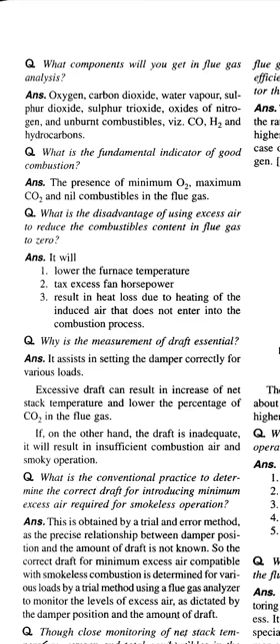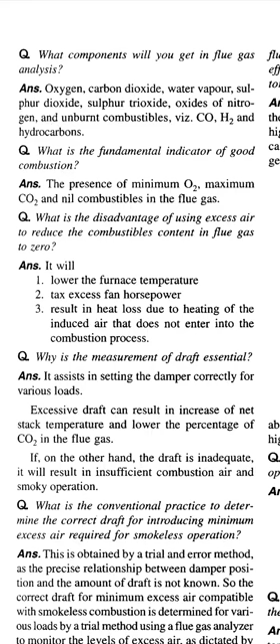Question. What are the disadvantages of using excess air to reduce the combustibles content in flue gas to zero? Answer. It will lower the furnace temperature, tax excess fan horsepower, and result in heat loss due to heating of the induced air that does not enter the combustion process.